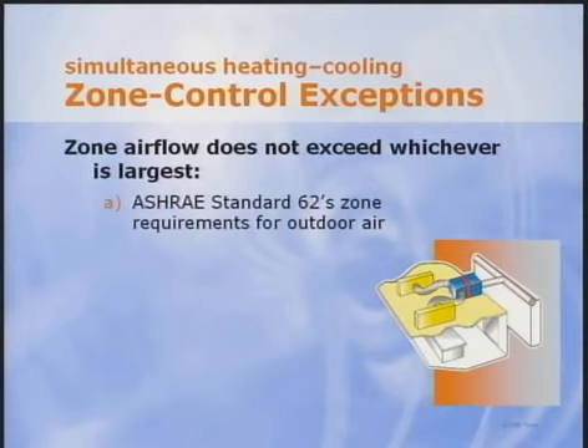Dennis will cover this in a few minutes. Since this results in high energy usage, exception A isn't used very often on mixed air VAV systems. However, this exception can work very well for dedicated outdoor air systems, since it allows all the ventilation air to be delivered to a zone to be reheated if necessary. There's another exception, that of 0.4 CFM per square foot.